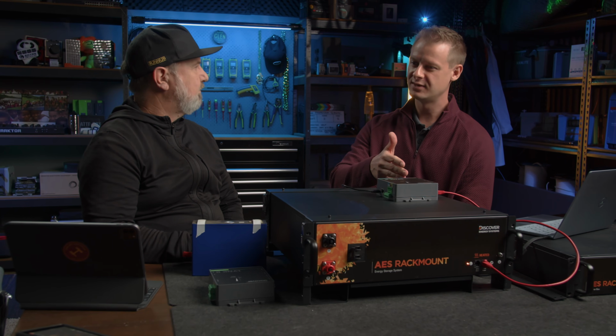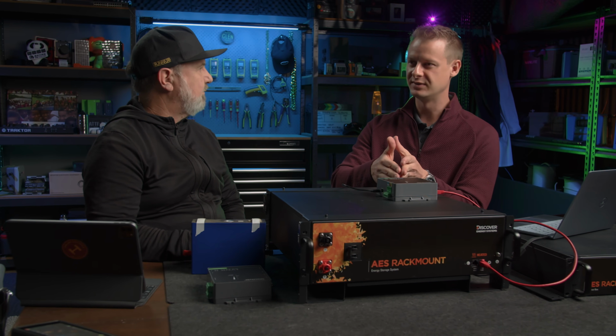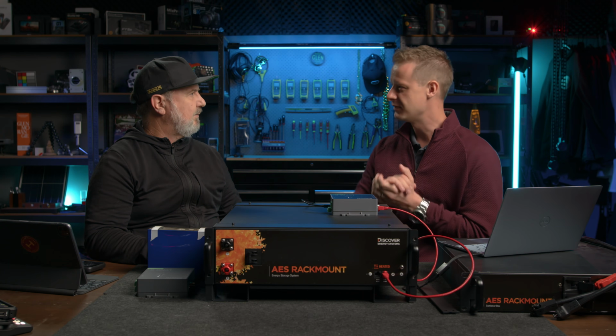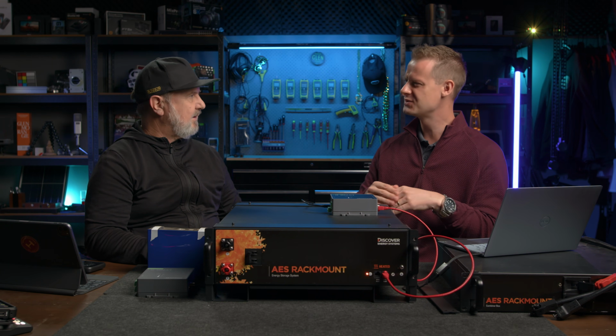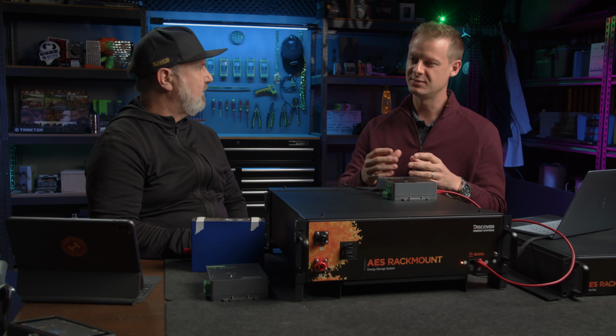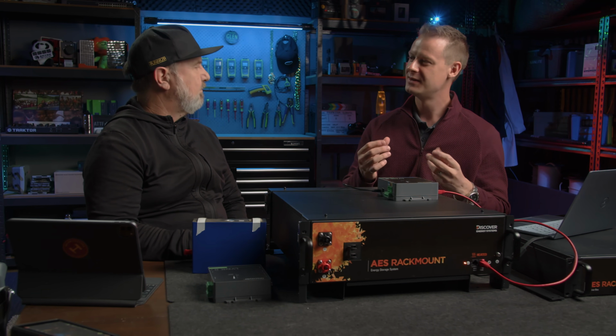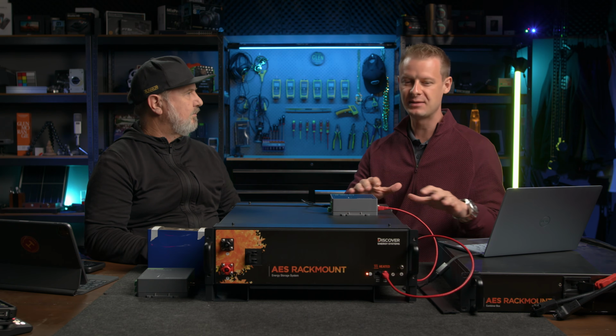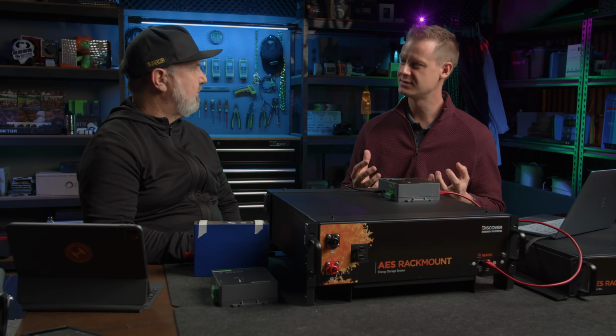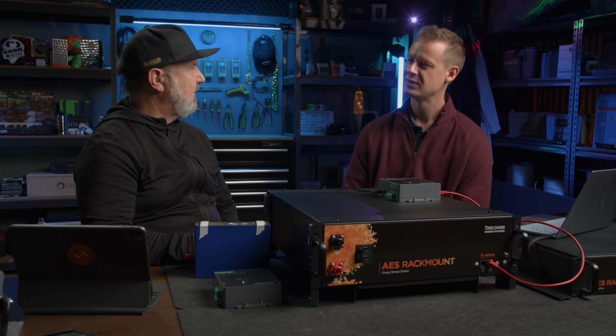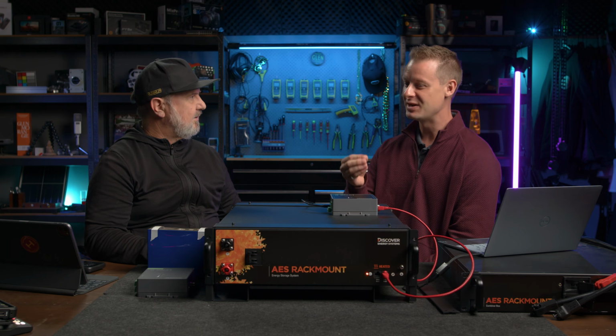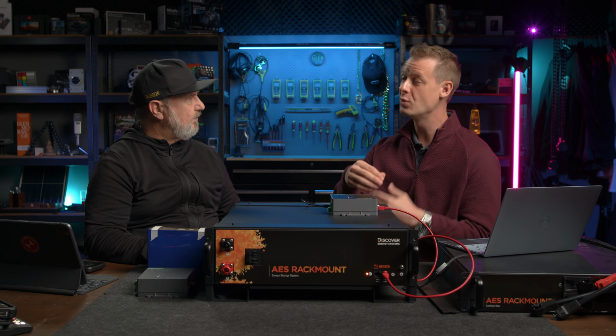The balancing will be triggered at a certain point, I believe around 3.35 volts per cell. As long as you're above that, you'll see balancing, but it really starts to shine when there's a trickle charge. You're seeing about an amp per battery, and that's when the balancing really takes hold and is effective. That's another benefit of open loop charging.